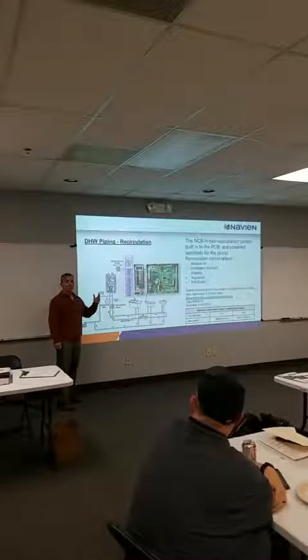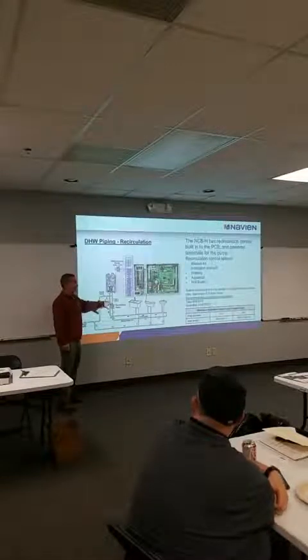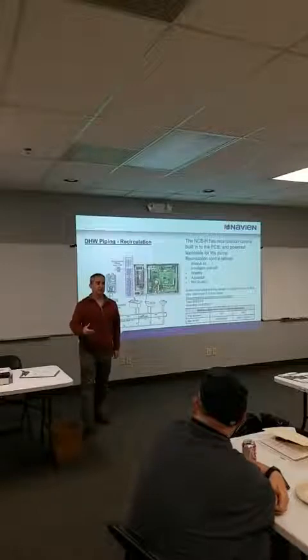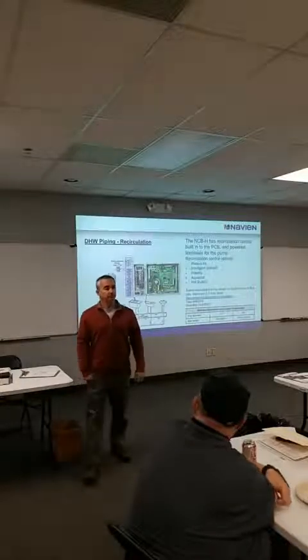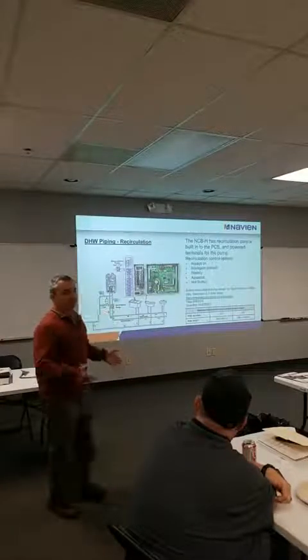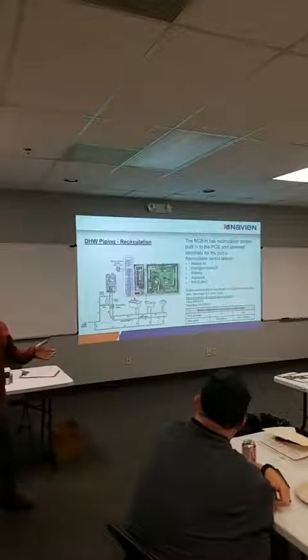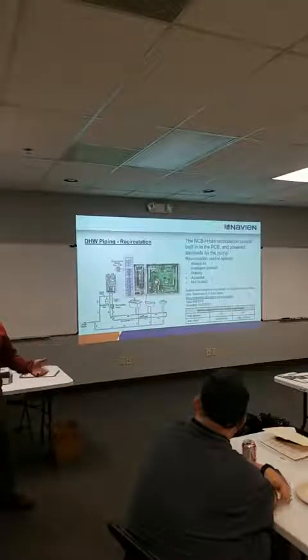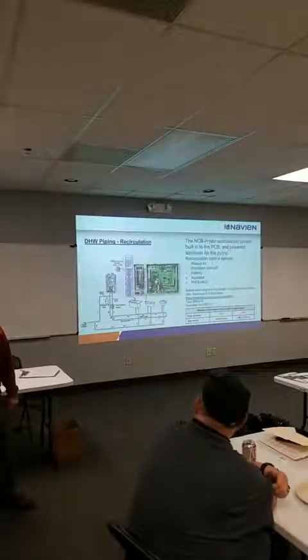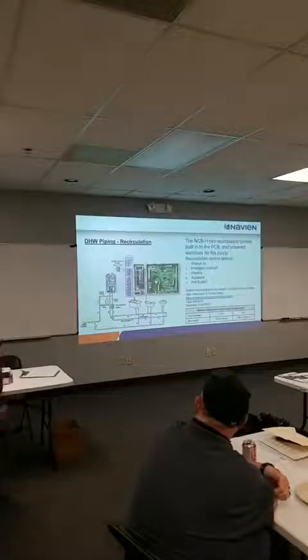When you close the faucet, that valve rolls back and it goes into heating mode. So we consider maybe a 10 to 12 minute max runtime for hot water usually, if you're taking a shower, filling a hot tub or something, a whirlpool, and then kicking back into heating.